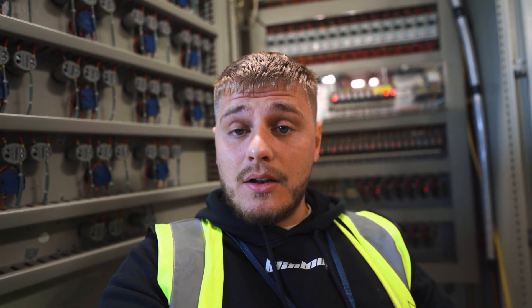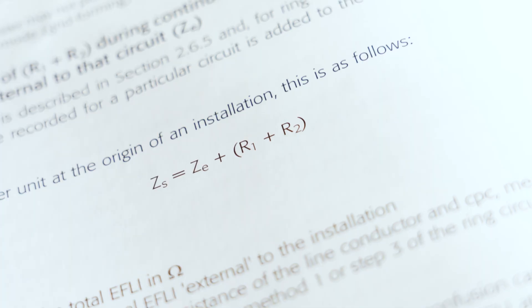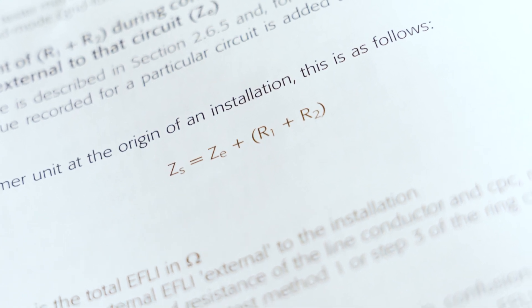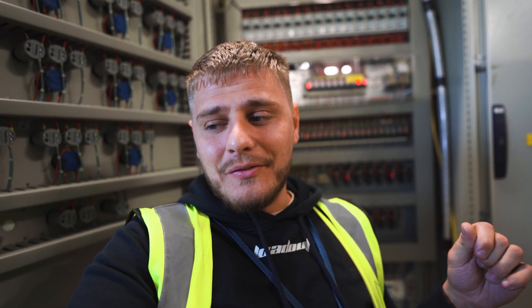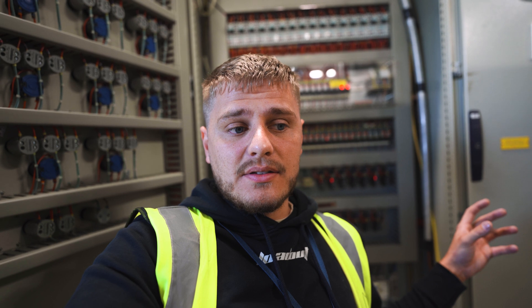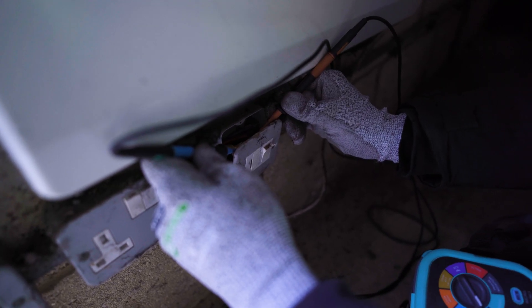You have to get a Ze as part of an initial verification or an EICR. You can get that value and then add on your R1+R2 — since resistance and impedance are essentially the same — so you're getting your external impedance and adding on the resistance of your circuit to calculate your Zs. Method two, calculation, is actually the preferred method because it involves less live testing, but everyone on site just uses method one and actually tests it.